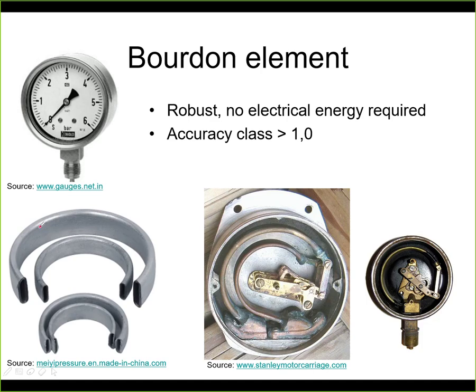This here is the Bourdon tube itself, just the Bourdon tube without the ends. It initially starts as a tube that is flattened, and then during the assembly process they solder the lever system to one end and the input port for the pressure gauge to the other end.